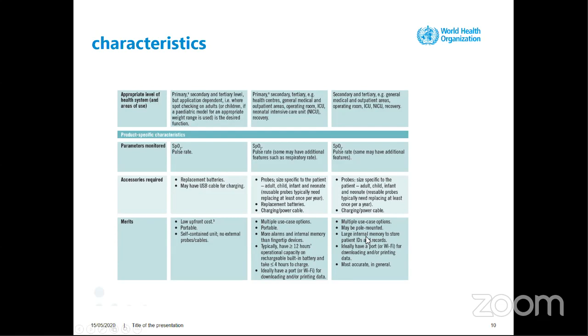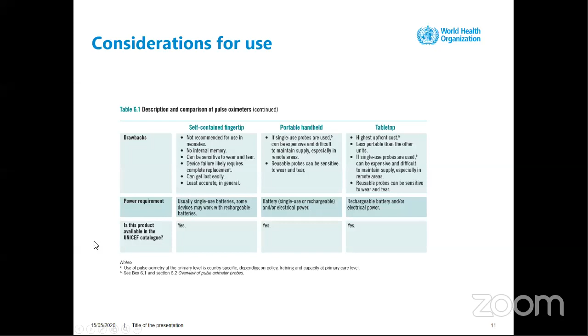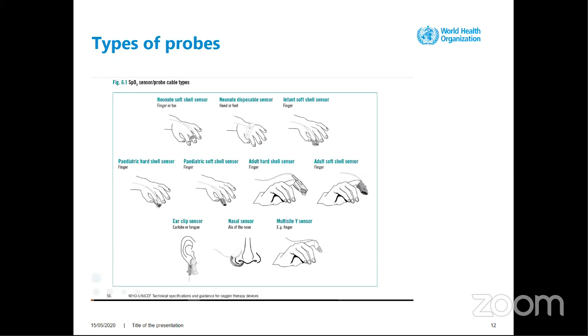We also have some drawbacks. For example, the fingertips are not recommended for use in neonates or very small children, can be sensitive to wear and tear, can be sensitive to temperature, and can get lost. The portable handheld is difficult to maintain, especially in remote areas. And the tabletop is of course less portable, and the reusable probes can be sensitive to wear and tear too. Everything will have to have its own catalog. Right now, they are in the UNICEF catalog, but also in the WHO catalog, and I will show you a screen on that. The book has the different sensor, probe and cable types, and of course we suggest some of them as best options.